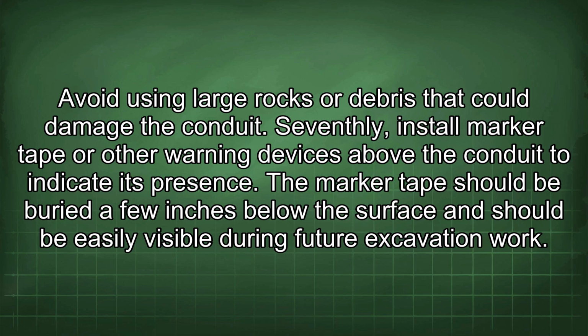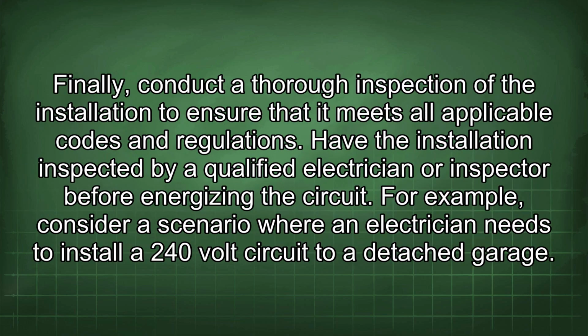Seventhly, install marker tape or other warning devices above the conduit to indicate its presence. The marker tape should be buried a few inches below the surface and should be easily visible during future excavation work. Finally, conduct a thorough inspection of the installation to ensure that it meets all applicable codes and regulations. Have the installation inspected by a qualified electrician or inspector before energizing the circuit.